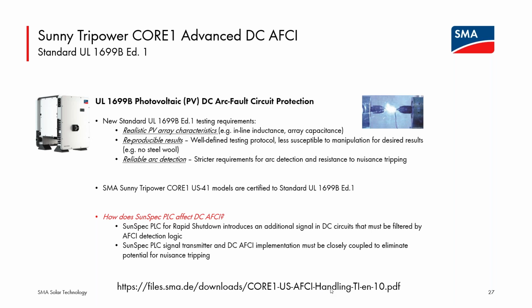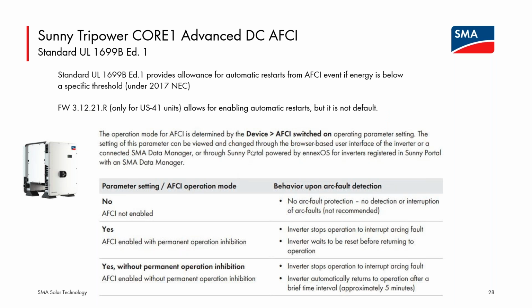That functionality is now allowed in the firmware, but it is not turned on by default. So the CORE1s with the new firmware still will require manual restart for arc events, but it is now possible to go in and choose, with AFCI on, to select this yes, but without permanent operation inhibition. In clear translated language, what that means is it does not require manual restart if the code allows an automatic reset. So there will be an interruption of power produced, but it is possible to have the inverter attempt to automatically restart from low energy, quickly extinguished arc events. Again, it's not on by default, but this functionality is there once the firmware is updated to 3.12.21 or higher.